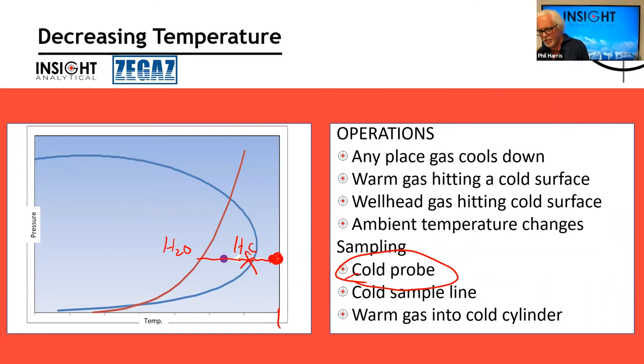So there's a bunch of conditions, and this is a common one in sample systems as well. Hitting cold spots in a sample system, whether it's for a BTU analyzer or a dew point analyzer, we can start to condense out hydrocarbons. As soon as we do that, we change the BTU value, and any analyzer that comes after that reads the wrong dew point.